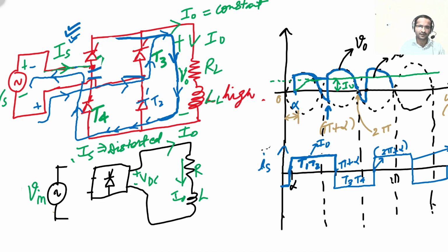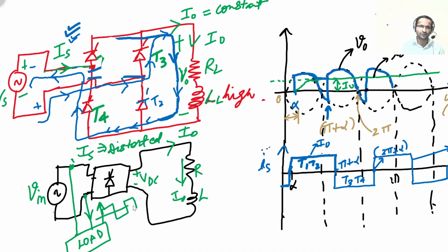But when we connect it through some converter or rectifier, it becomes a square wave. Now what is the disadvantage of this? To this source, some other loads are also connected in parallel. So these loads will also have this non-sinusoidal current. If you connect the converter, the current that flows through other loads will also be a non-sinusoidal square wave.